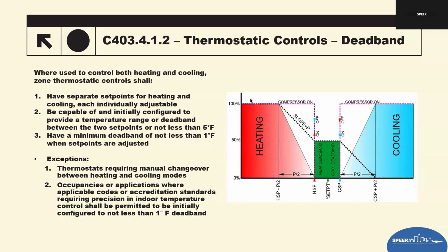So have minimum adjustment deadband. When someone manually adjusts the set point, the system must maintain at least a 1 degree separation between heating and cooling set points. So even if the occupant pushes these settings as close together as possible, the thermostat will not allow them to eliminate a deadband entirely. So there are 2 exceptions here.